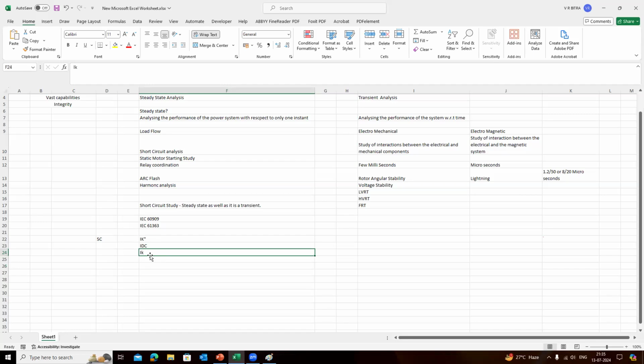Okay, what are the different currents that you have found? These three currents: one is the subtransient current, IK double dash; the transient current, IK dash; and the DC component of the short circuit, that is IDC; and the steady state current, that is IK. So these are all the different currents which you can study while performing the short circuit.